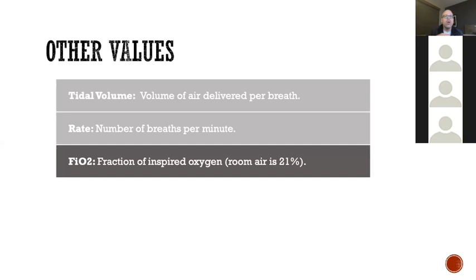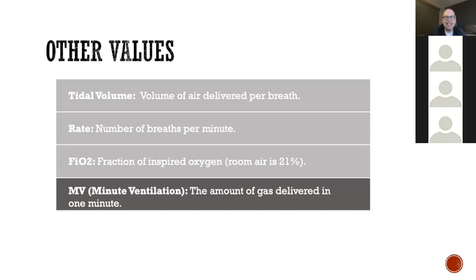MV, that's our minute ventilation. So that's the amount of gas delivered in 1 minute. That's a real good number as well to look at on your ventilator screen and see what that is, because that's going to tell you how much the patient is actually breathing. Especially if they're in SIMV, where they can take varied amounts with their extra breaths, I want to look and see how much they are actually breathing.